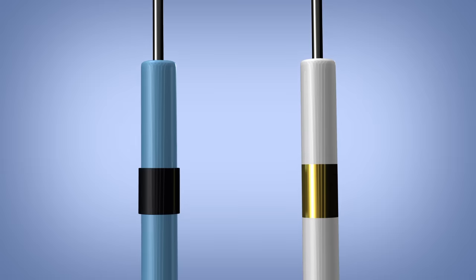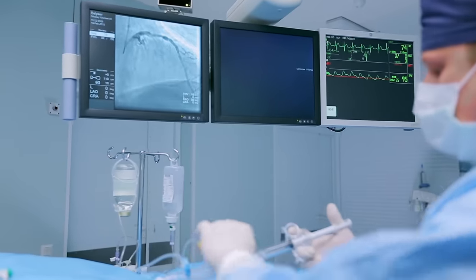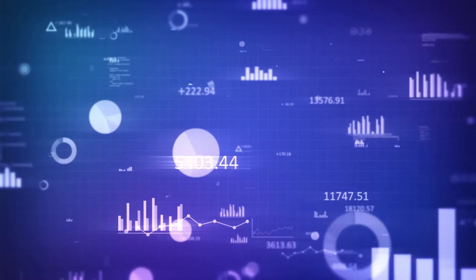Visiband can be applied thinner than traditional marker bands or machined markers if radiopacity requirements are lower, which potentially reduces material costs.